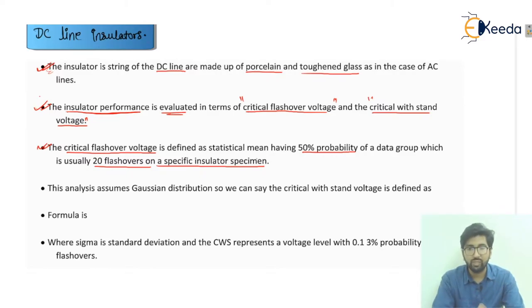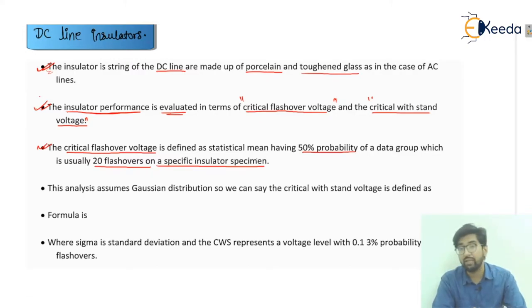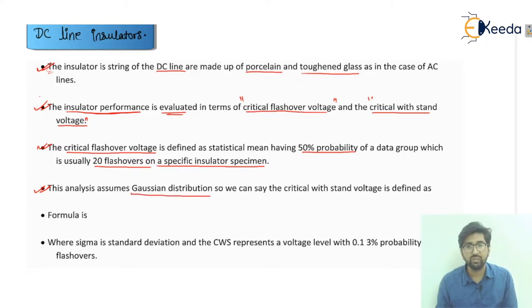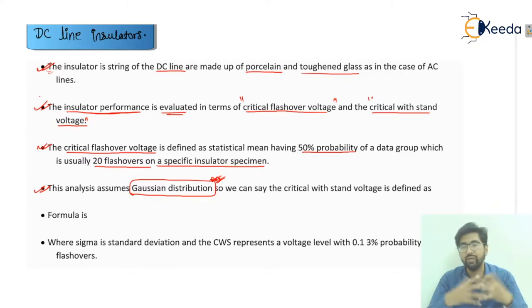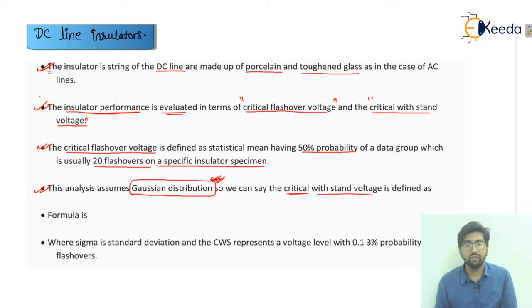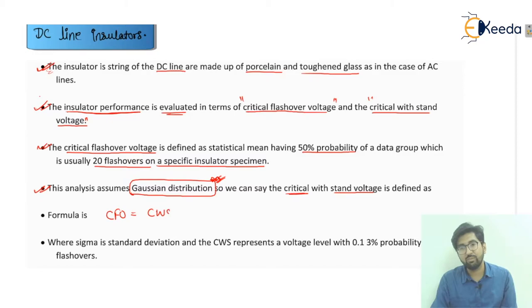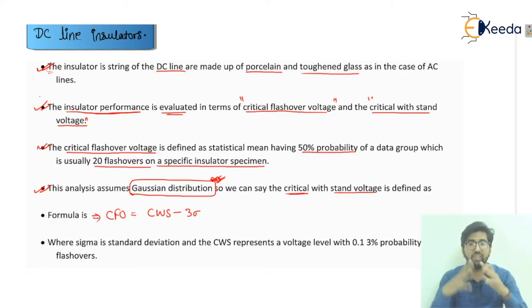The critical flashover voltage is defined as a statistical mean having 50% probability of a data group, which is usually 20 flashovers on a specific insulator specimen. So it is a kind of statistical mean — you are taking the average value — with a 50% probability of a data group. The analysis assumes a Gaussian distribution. Using that, the critical withstand voltage (CWS) formula is: CFO = CWS − 3σ.